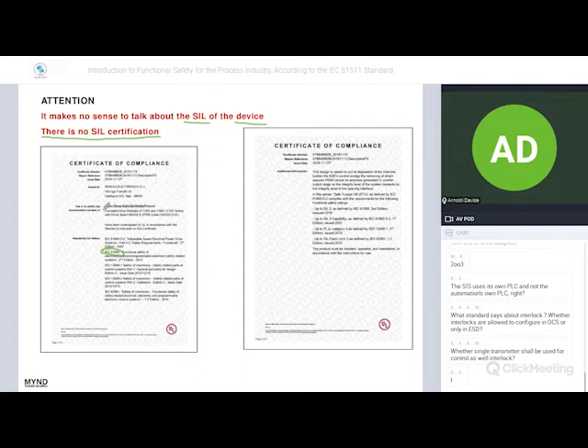So, for example, this power drive system is possible to install in a function that should respect SIL 3 capability or SIL 3 requirements. This means that it is not the SIL level of the device. We are speaking again about the SIL level for the function. We can install this device in a function that has to answer a SIL 3 requirement. This is the difference with the SIL level that we normally use for a device. No, we have to speak about SIL level for the function only.